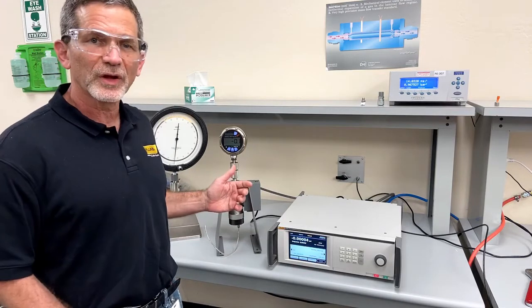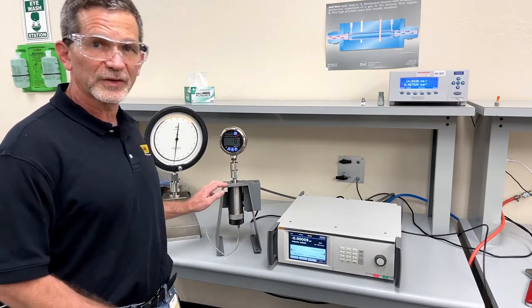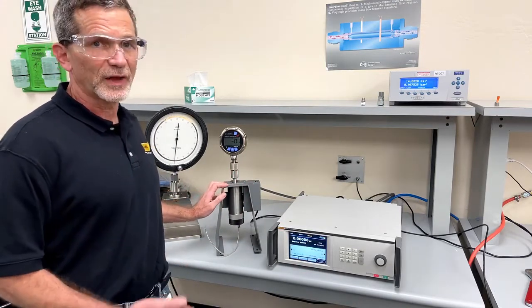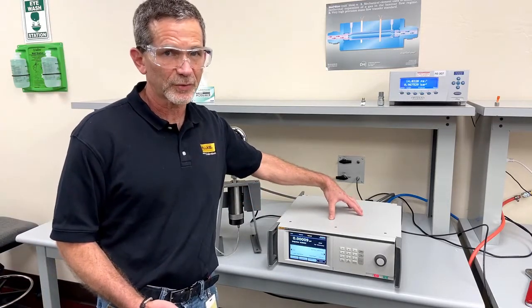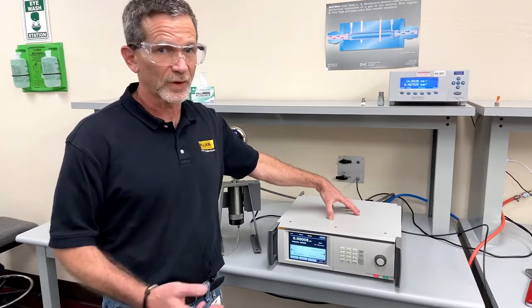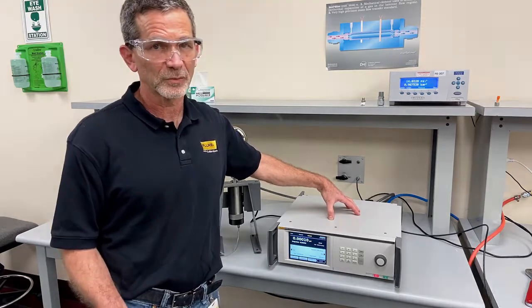You heard a second ago the burst of air, that's the pressure booster that we offer, that allows us to achieve the 6,000 PSI supply pressure that's necessary to control up to 6,000 PSI.